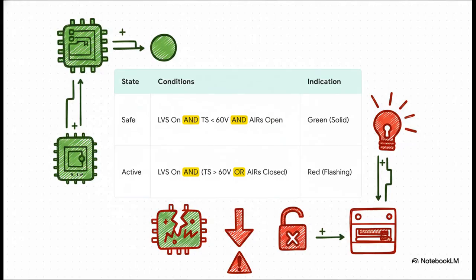Period. The whole logic behind the TSAL is built on what I call a default-to-danger principle. It's actually really clever. For the system to say, okay, I'm safe, and show you that solid green light, three things have to be true at the same time: the low voltage system has to be on, the tractive system voltage has to be proven to be under 60 volts, and the main high voltage contactors, the AIRs, have to be physically open.